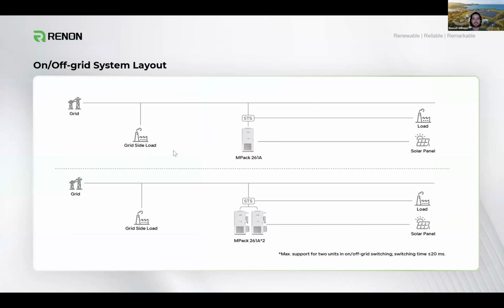This gives you a picture of some of those different on-grid, off-grid switching load profiles. The way this is wired up, you can have the MPPT cabinet. This would be an example of the model with both the MPPT cabinet and the STS added. You can see them in the graphic here. They're not really depicted in the top one, but here the solar would run directly into the MPPT cabinet, which would then directly DC charge those cells. Those cells are then connected through an STS to the load. So it's 2 units per STS.